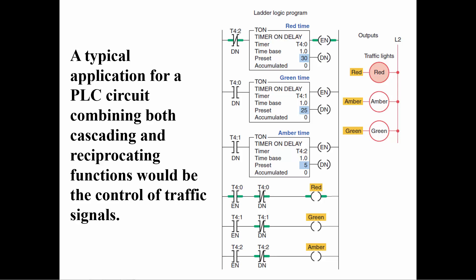This change of status will cause the second rung to become false and timer T4:1 to reset its accumulated value and done bit. When the done bit of T4:1 is zero, the third rung becomes false and T4:2 is false. When T4:2 becomes false, its accumulated value is reset to zero and the done bit is set to zero. On the next scan cycle, the first rung will become true and the timing sequence will begin again.